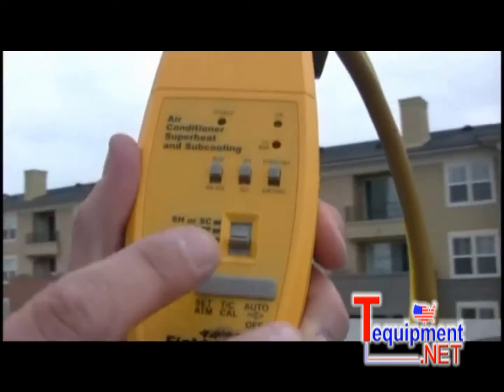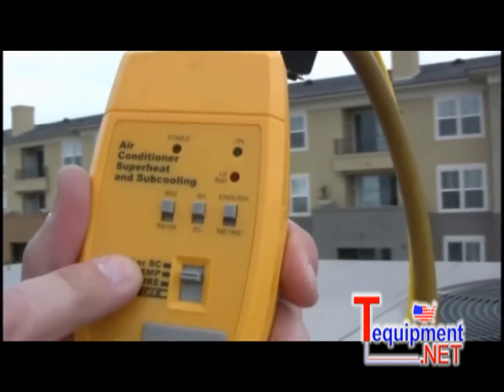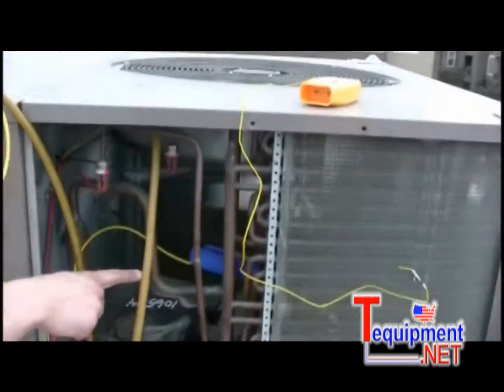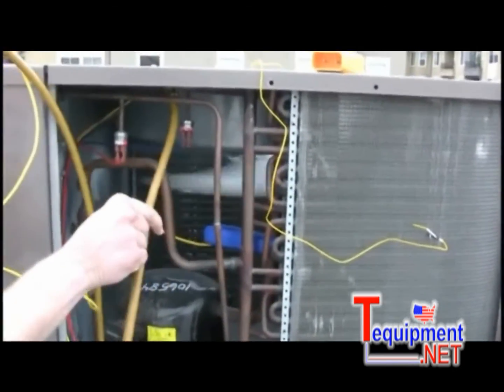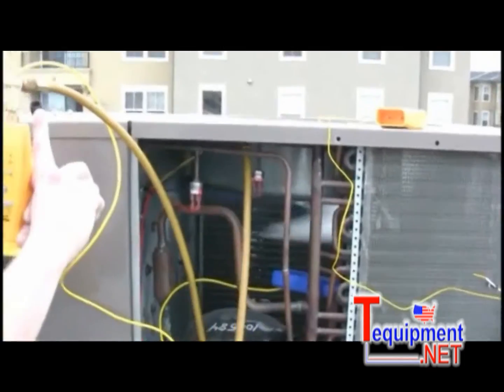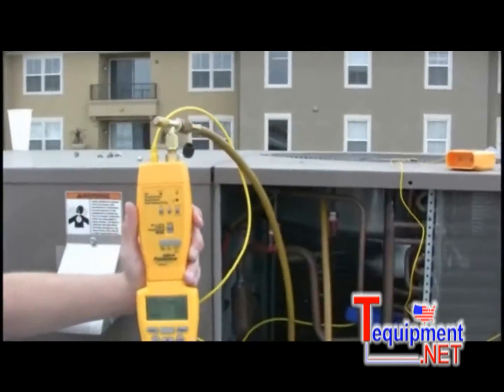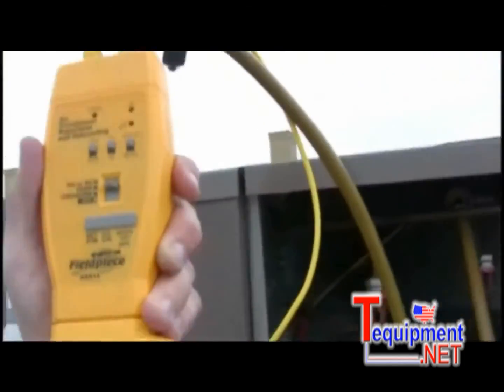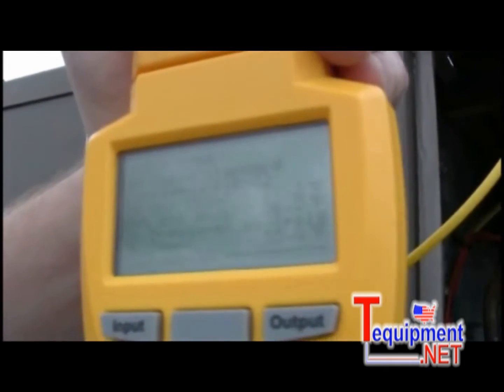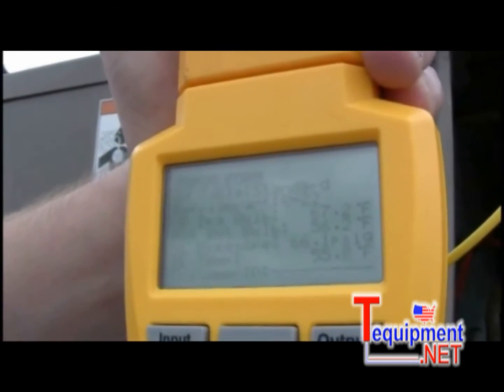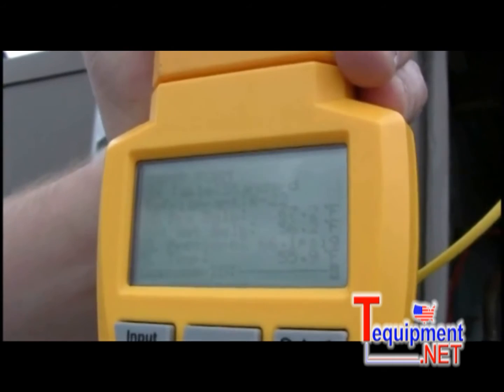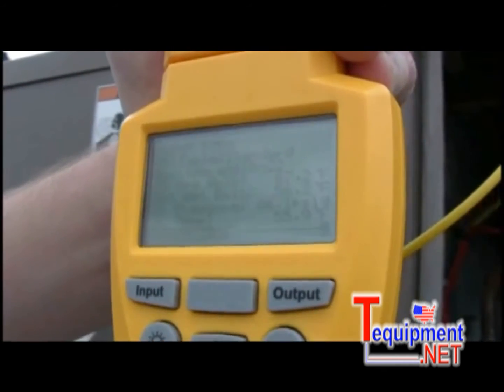I can use the same head. I'm going to go up and put up the temperature. Now down here below we have the pipe clamp attached to the suction line. And we also have the refrigerant cord going directly to the ASX14 here. So on suction line temperature, I'm just going to press enter to start taking the temperature. You see that I have a 55.8 degree suction line temperature. Looks pretty stable. I'm going to press enter to lock that in.